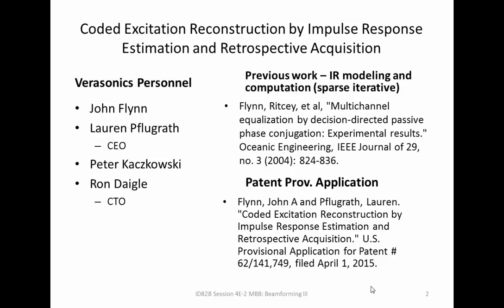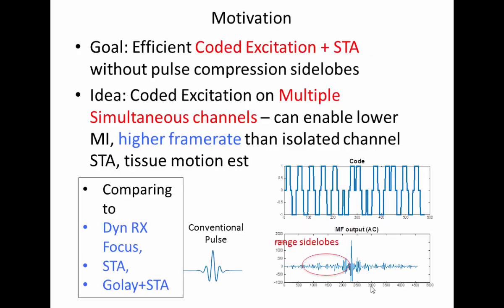This is coded excitation reconstruction implemented through impulse response estimation and retrospective transmission and beamforming. There's an earlier paper applying a similar technique to ocean acoustic channels for telemetry experiments. The goal is to have efficient coded excitation synthetic transmitted aperture without pulse compression side lobes, using simultaneous transmitted channels. This can lower the achievable mechanical index, achieve a higher frame rate than isolated channel synthetic transmit aperture with Golay coding, and also enable tissue motion estimation processing.